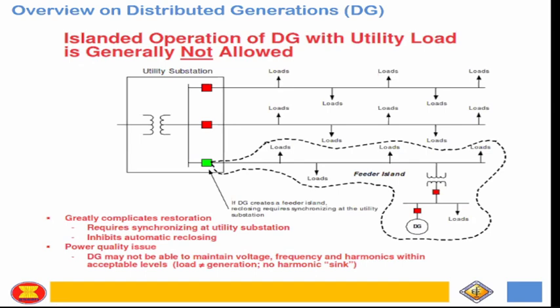frequency, because when you have a load, you operate your governor, and the governor is directly proportional to the frequency as well as the speed of the generator. When it's deloaded and there's a load rejection, it will overspeed, and the speed is directly proportional to over frequency. So that's why you get over frequency and then over voltage. Somehow the power quality is compromised. That's for the case if the generation is larger than the load.